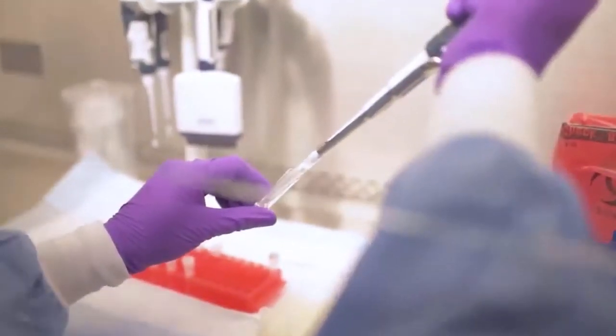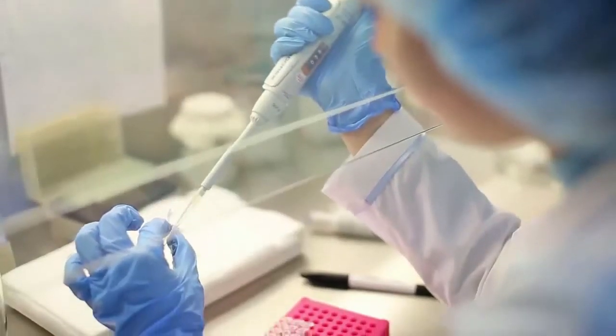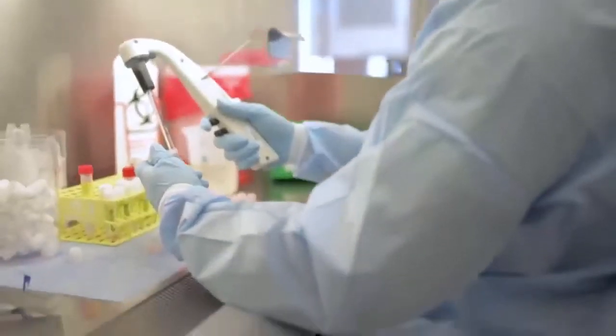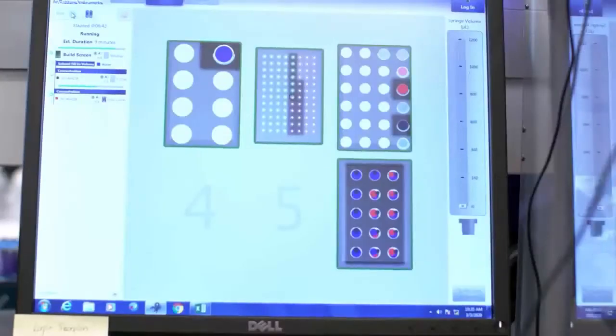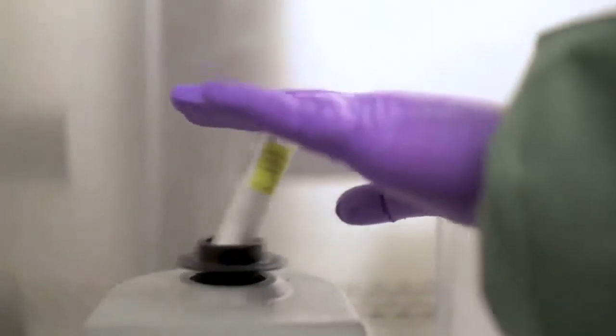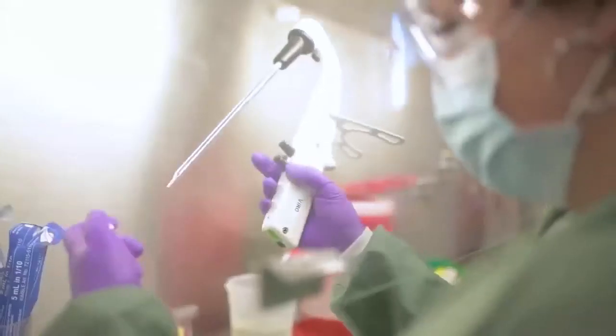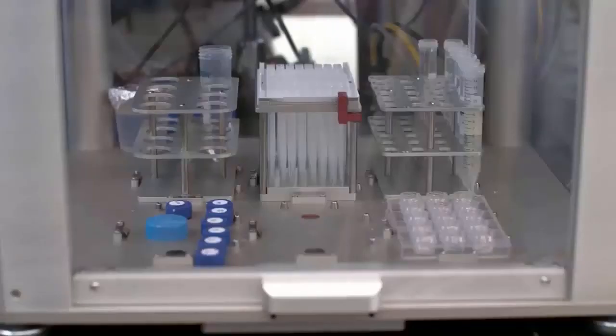But despite these advances, these synthetic tests are still not widely available. They've been adopted extremely slowly due to regulatory and safety concerns. Europe didn't recognize the synthetic protein as an alternate endotoxin detection until 2015, and the FDA in the US didn't approve the first drug that used an endotoxin test based on the synthetic protein until 2018. And earlier this year, the American Pharmacopoeia, which sets the scientific standards for drugs and other products in the US, declined to place the synthetic protein on equal footing with crab lysate, claiming that its safety is still unproven.